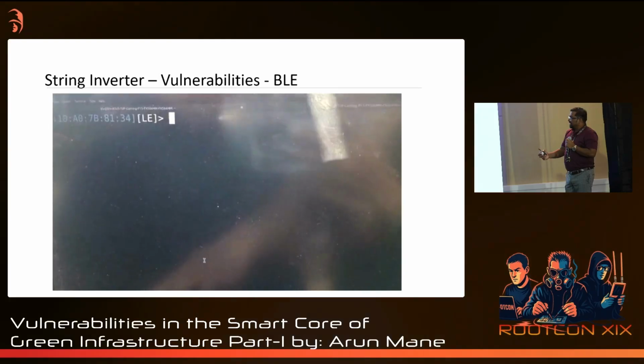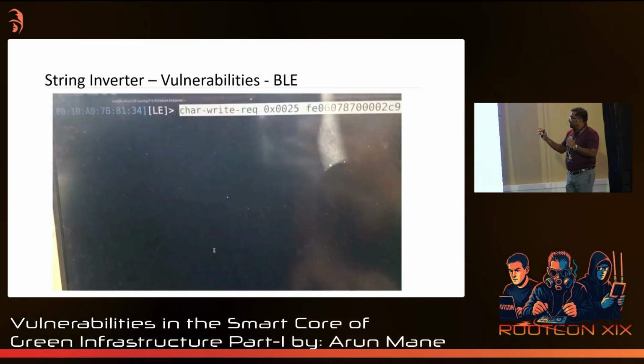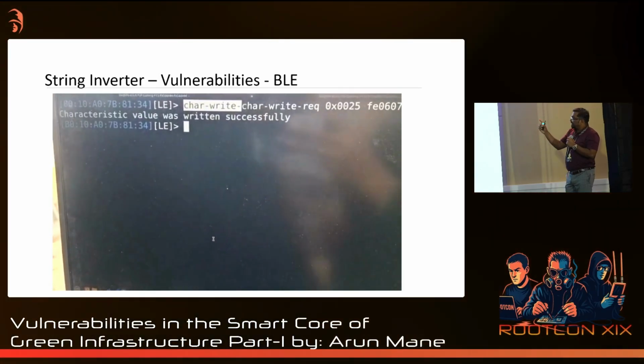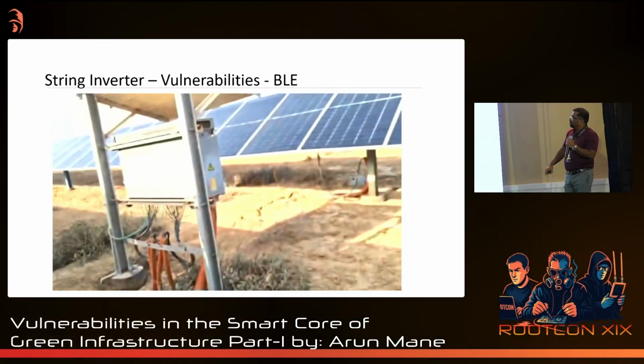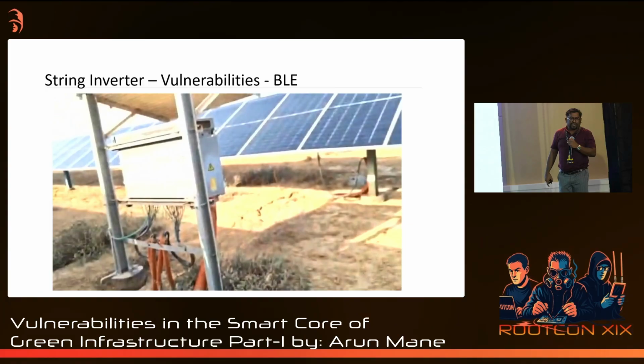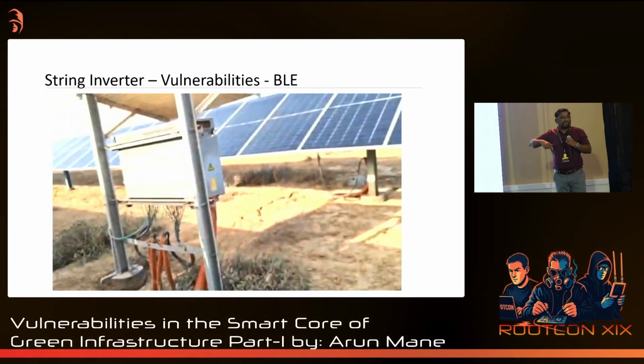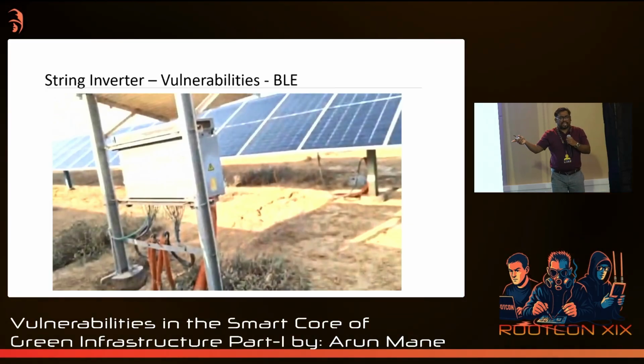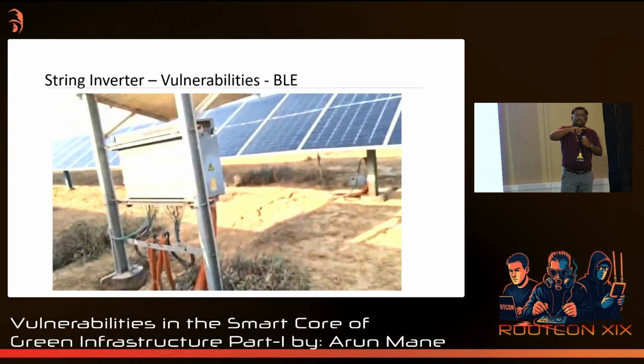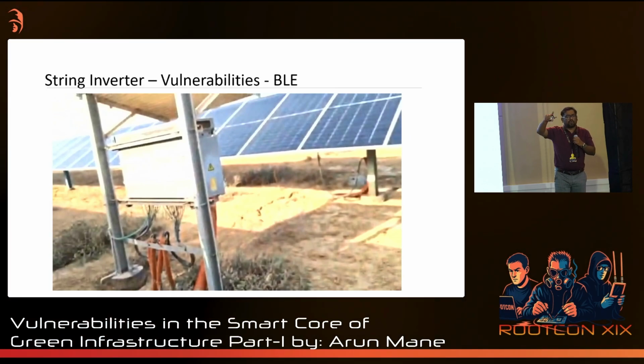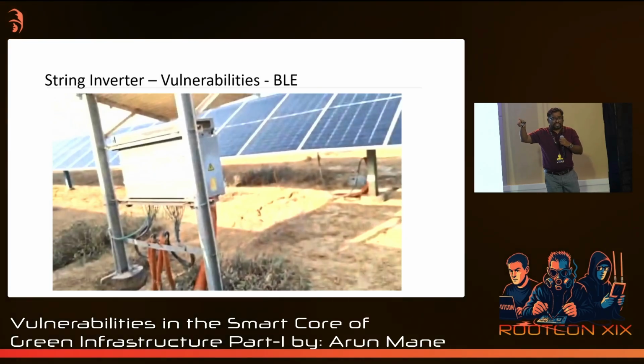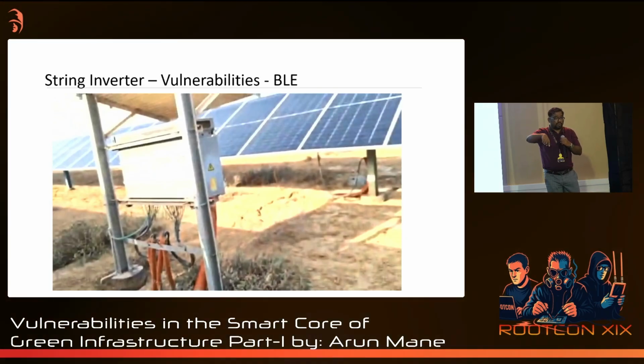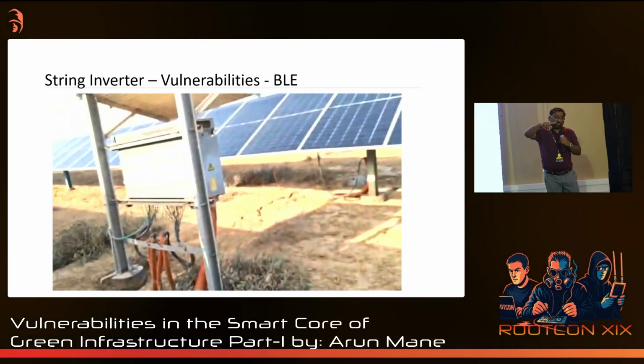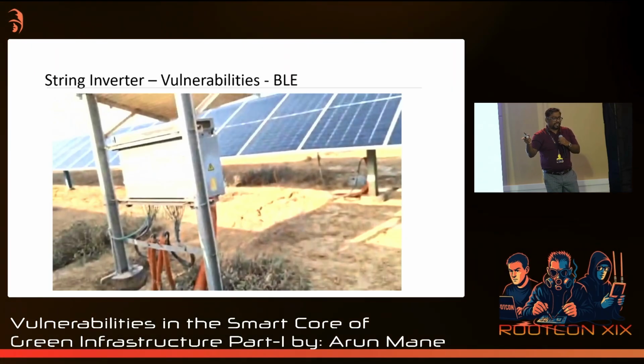So here he writes the command. The value is written successfully, and the inverter shuts down. At the same time, we checked the SCADA system and saw the DC voltage production drop to zero, with the status showing turned off.